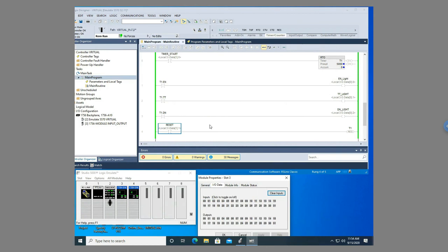So when would you use an RTO in industry? Well, one example for this possibly might be in a shift, you might want to keep up with your downtime. And so every time a line goes down, you might want to count for accumulated value and then hold that once your line goes back up, but you still need your total time. And so you hold that value until the next time it goes down. And then it would start counting right from the moment it left off. So that's an example of where you might use an RTO in industry.